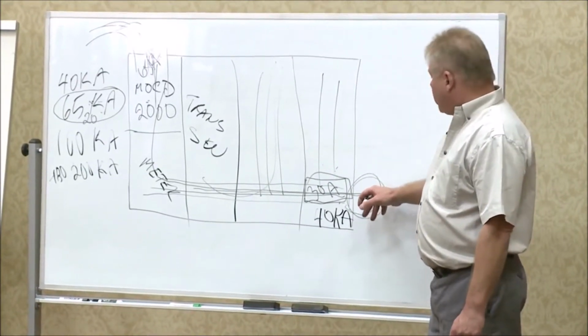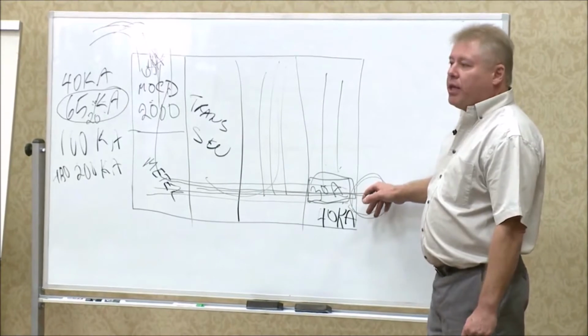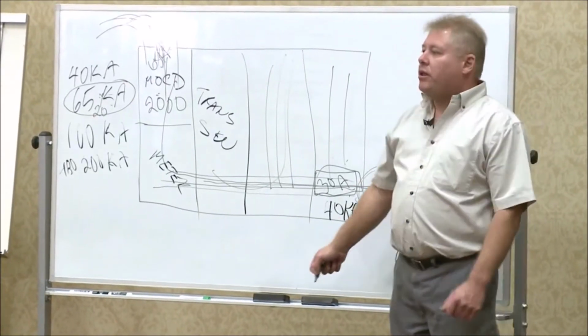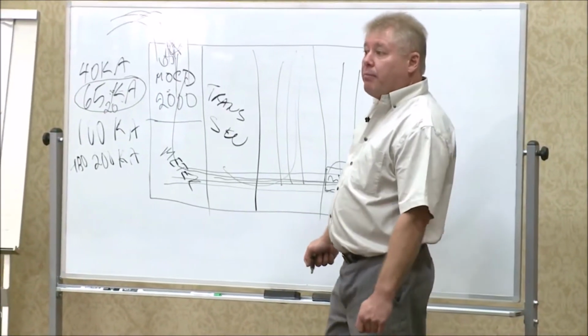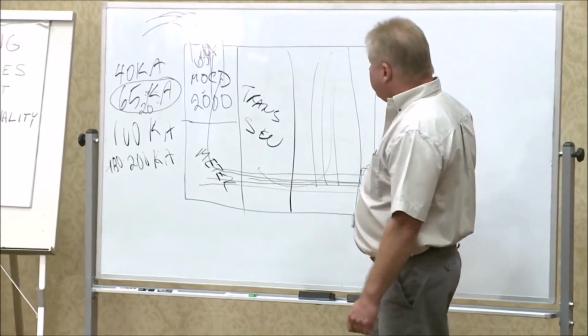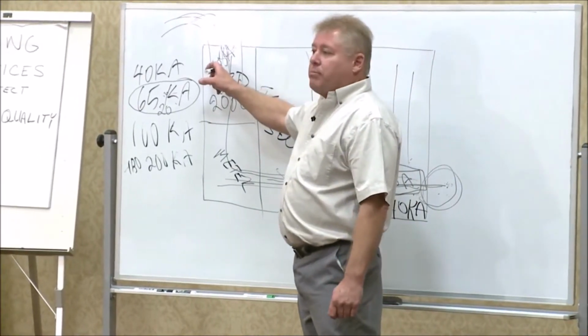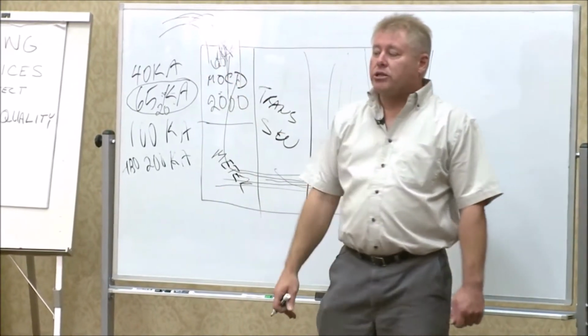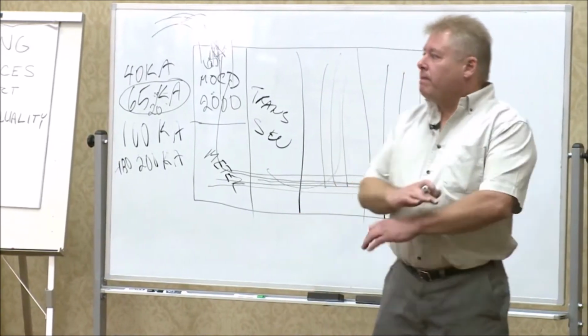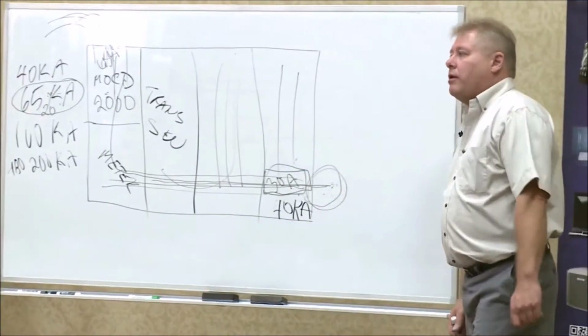If it's a lightning-type surge event, it opens up like a shunt and drives it to the neutral ground. That's why it's good to have a well-bonded neutral system. Allowing this to reach its maximum literally turns it off, so the surge is no longer coming into your building.